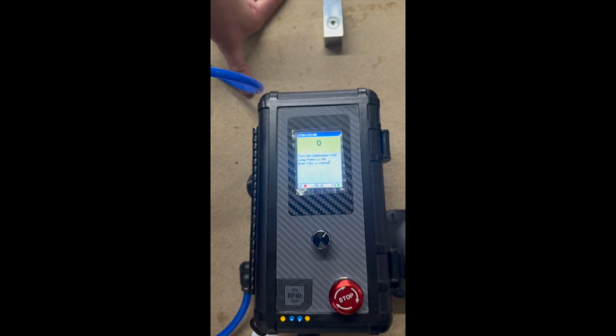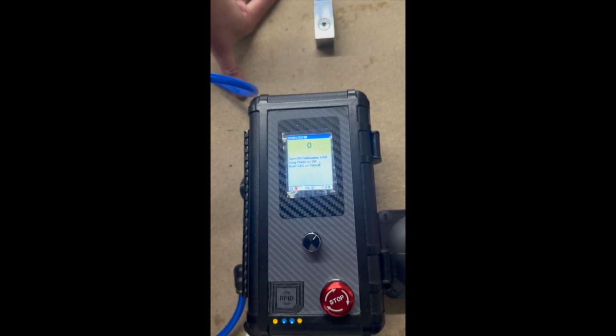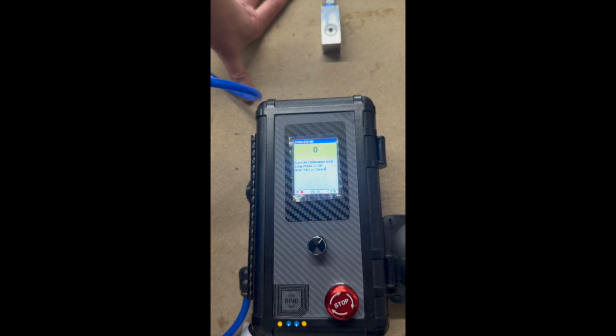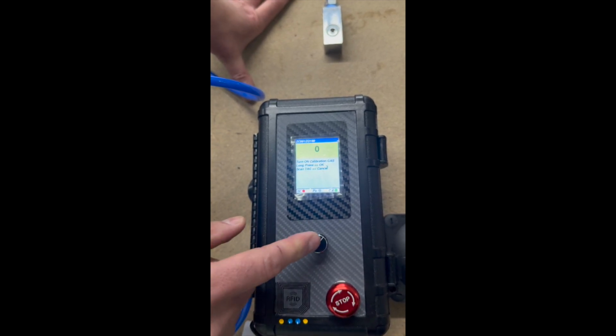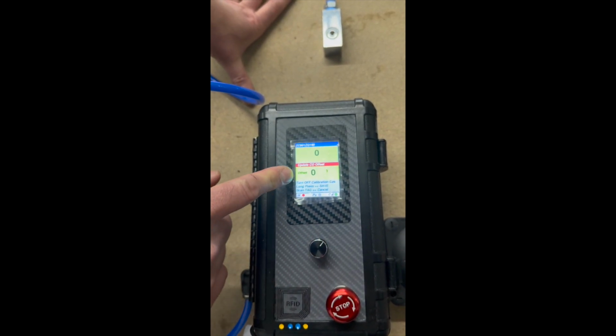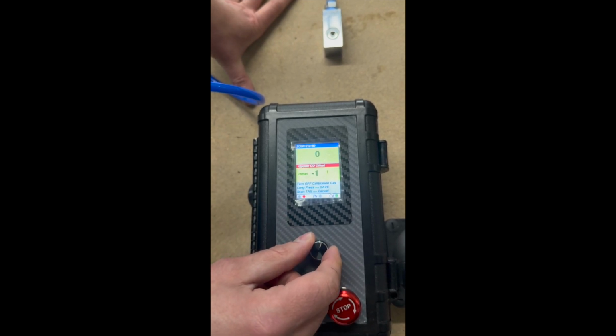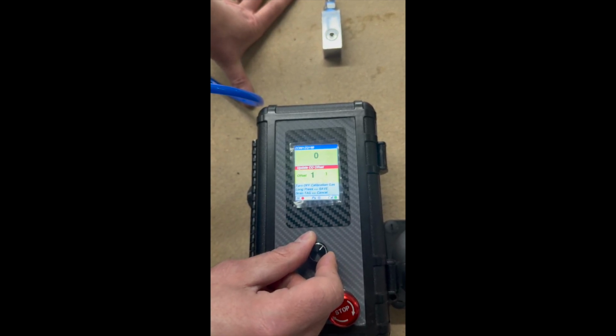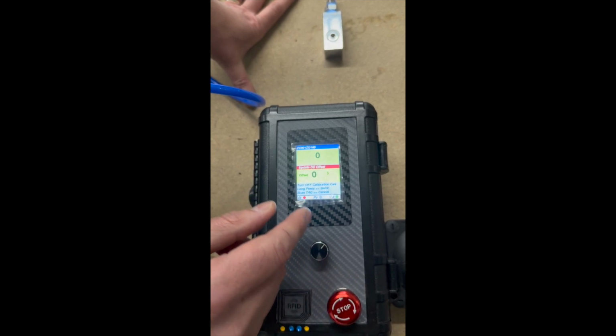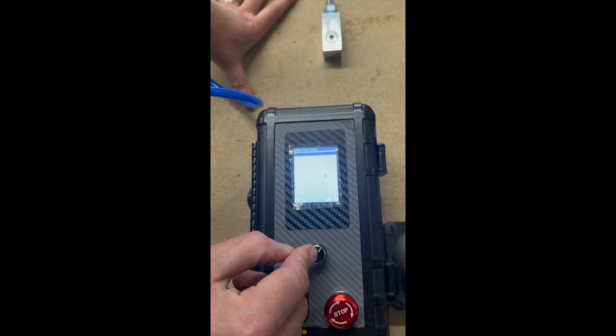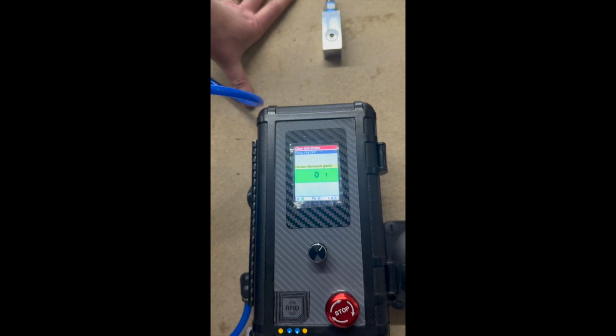Basically, what you have to do, you have to get a tank with a CO. Let's say that you have a 95% CO tank, you connect that tank here, you're supposed to read 95 here. If you are reading 95, your sensor is calibrated. But if you are reading 94, and that means you have one offset, you press on this, and the next screen you have the offset screen. You bring this to 1 or -1, however you like to calibrate up or down, and then that way you calibrate the tool. And this is pretty much it.